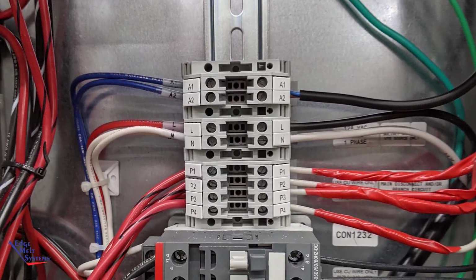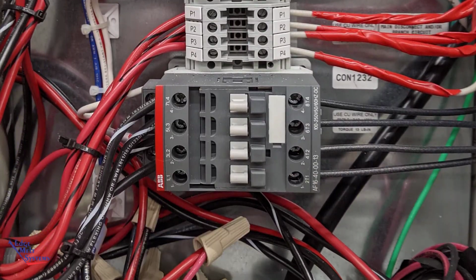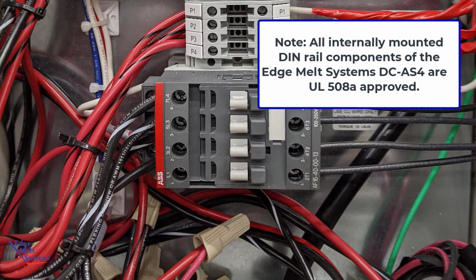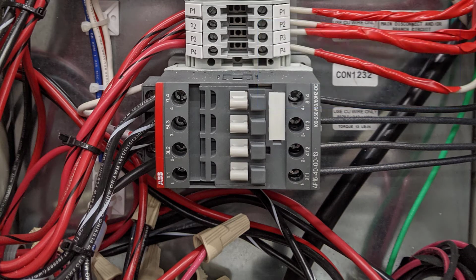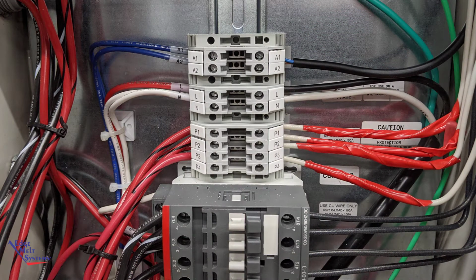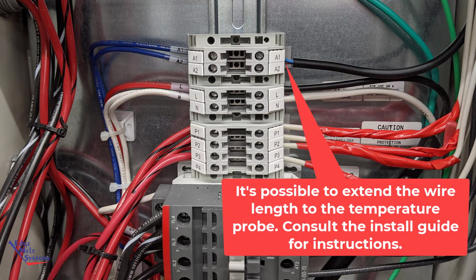Internally mounted DIN rail components are all UL 508A approved. Beginning at the top of the terminal block, we see the inputs for A1 and A2. This is for the non-polarized temp probe. The temp probe comes as a 10-foot lead and can be extended with standard wiring per the instructions in the install guide.